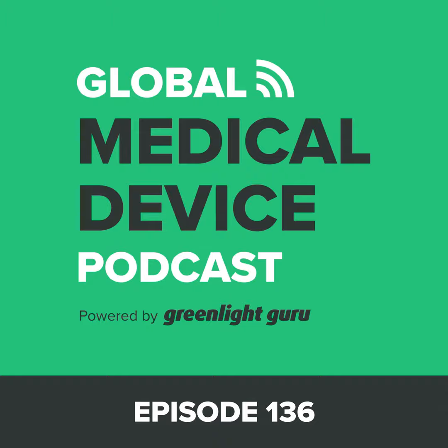In other words, devices that have been around for a while, where their safety and efficacy is well understood, where their performance testing requirements are well understood and accepted. And in fact, that particular program currently is limited to medical devices that fit into certain predetermined product codes. FDA has identified about 40 product codes thus far that are applicable to the Quality in 510(k) Review pilot. So there's a lot of similarities between all of these different programs.